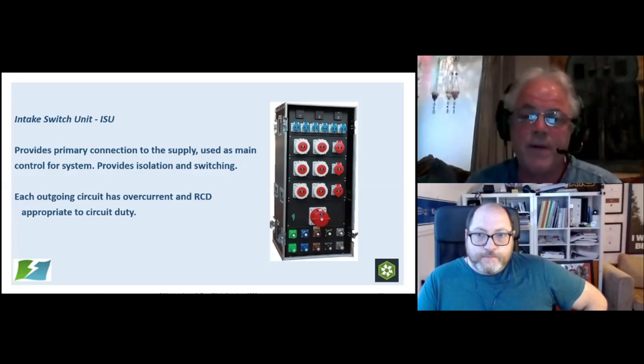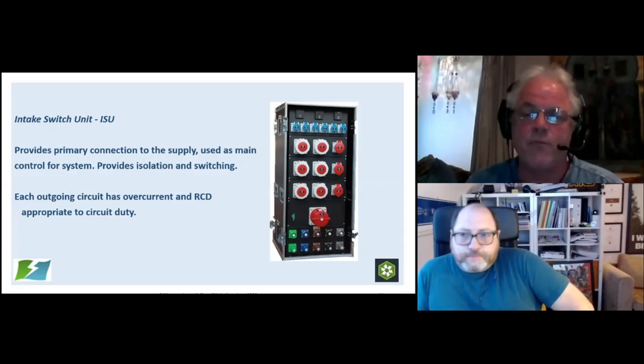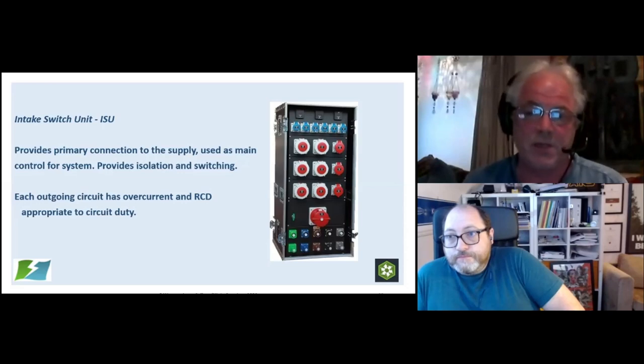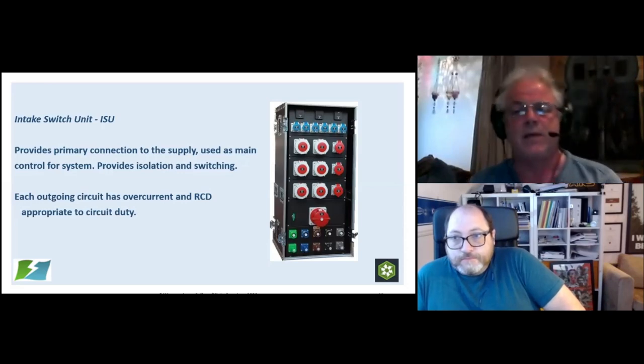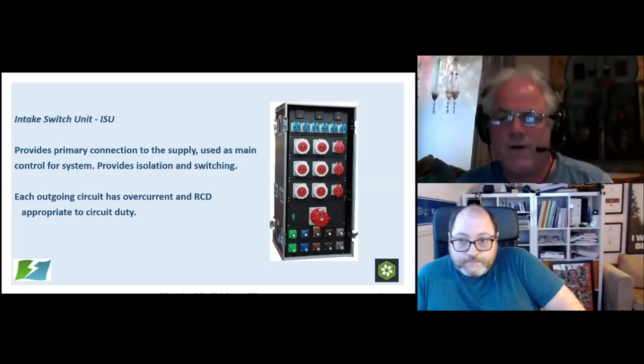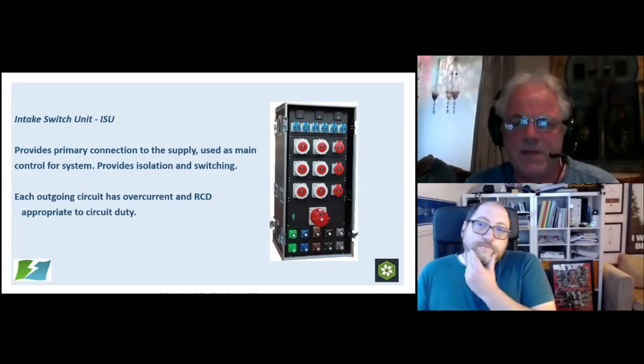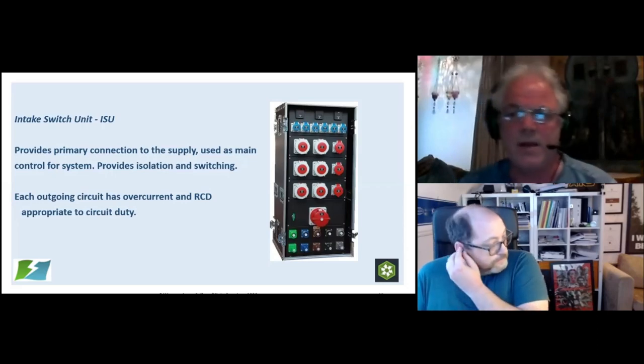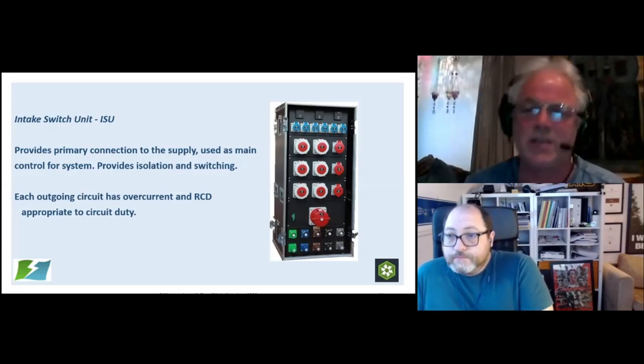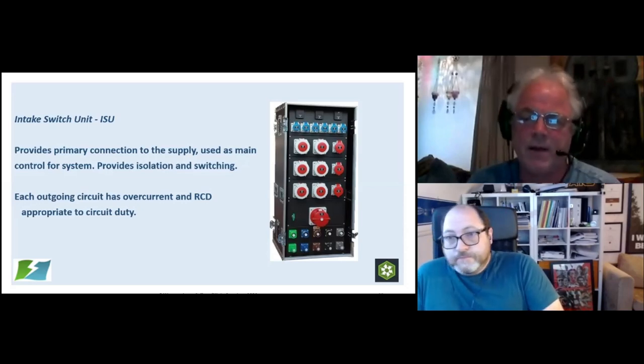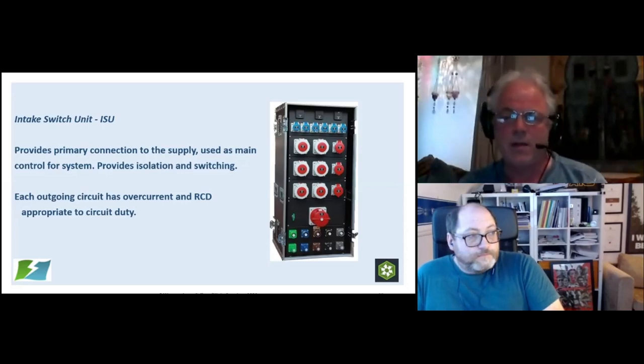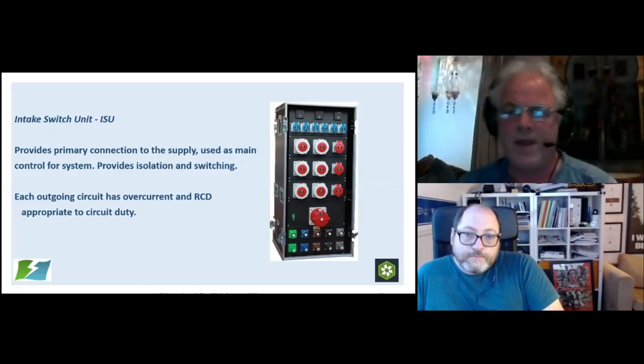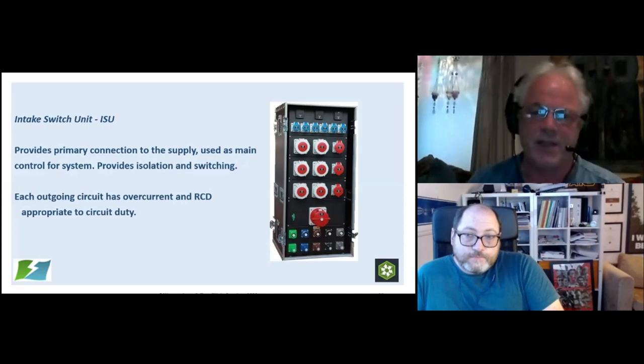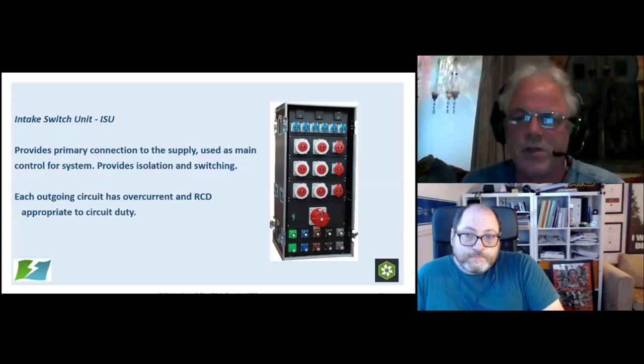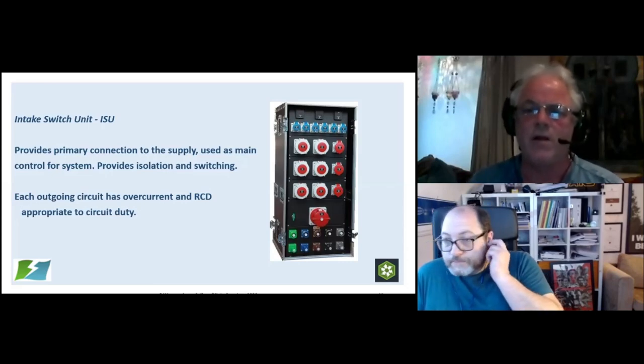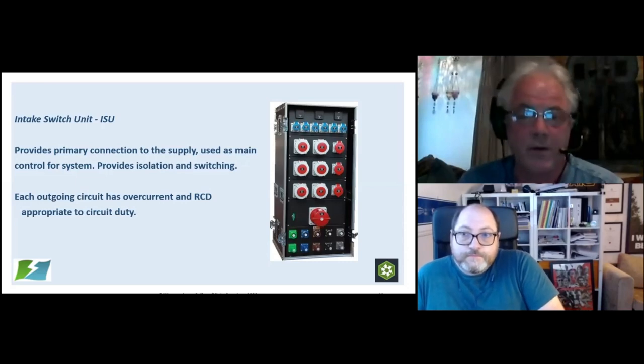The RCDs themselves, it's actually been in BS 7909 for a number of years that we can't use type AC, or we shouldn't be using type AC RCDs because of DC feedback. And this is something that's been covered by David and a few other members of V5. Paul has spoken about this, that different types of RCD, depending on what equipment you're plugging in, an AC type RCD, for instance, may be rendered completely useless by DC feedback from the equipment that you're actually plugging into it. So it tests out all right when you actually liven up the box, because you haven't got any equipment connected to it. As soon as you plug equipment onto it and it starts drawing a load, the RCD no longer works. Now, on a lot of temporary installations, because we're using such long lengths of cable, we are totally reliant on RCD protection. So if the RCD is not working, we are in a world of pain.